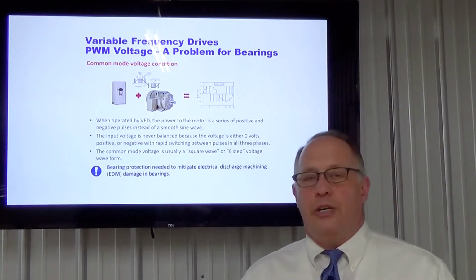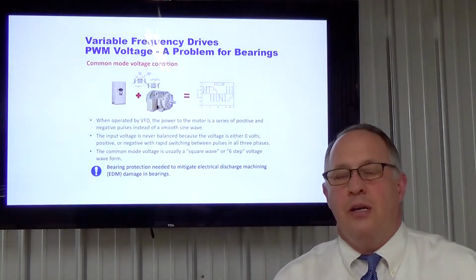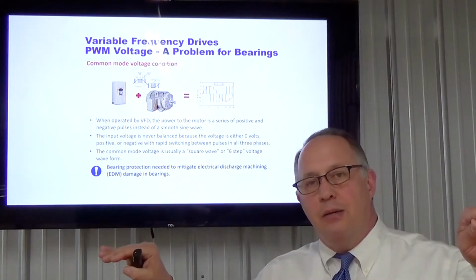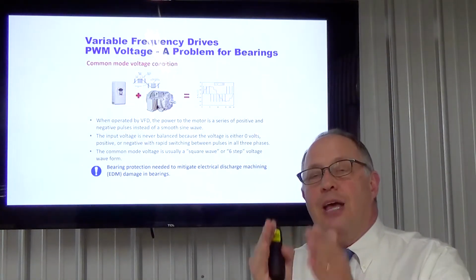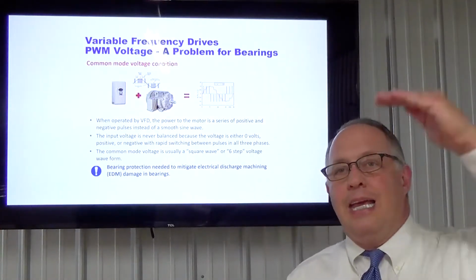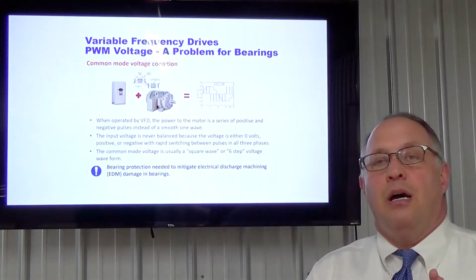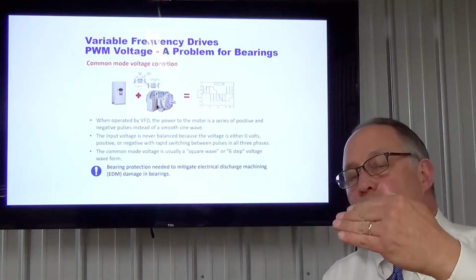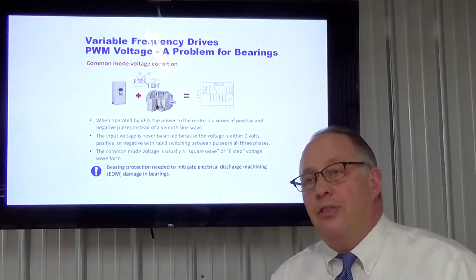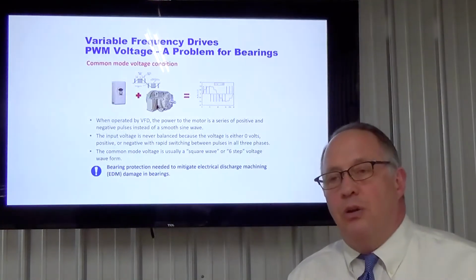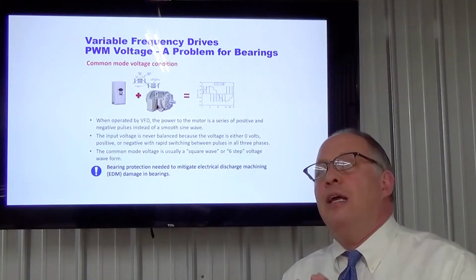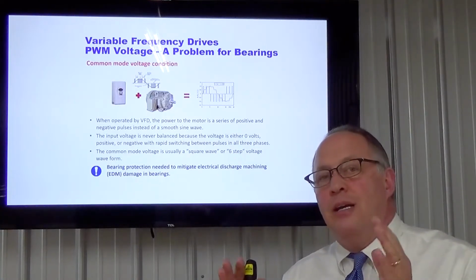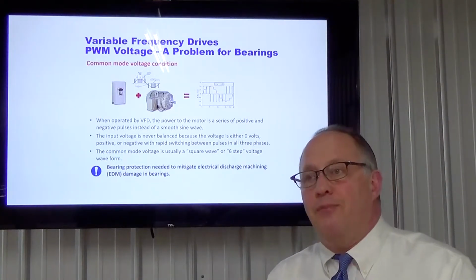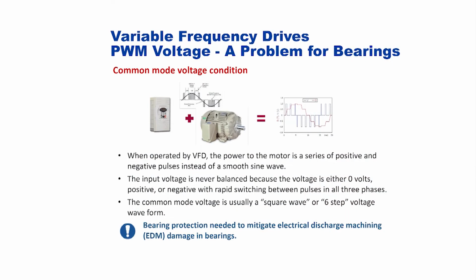In other words, we're taking the standard wave, converting it to DC on a DC bus, and then we're chopping the wave up and giving it amplitudes so that we can produce a waveform that simulates a sine wave. The motor is used to seeing that sine wave, but we use fast switching and different step functions in order to produce a waveform. You can see this one up here, and it can be a choppy waveform at that.